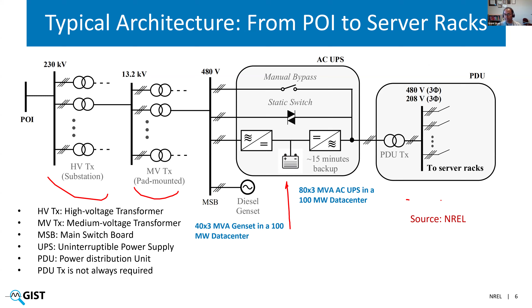What I want to focus more on is what is there within the IT rack. So we start with 480 volts today. Previous data centers were more towards 208 volts. And then we have these power supply units, which are hot swappable and arranged in a power shelf, where multiples of three are arranged in a single power shelf, because they're all single phase converters, but they are supplied by a three-phase supply. So they're distributed either using star or delta connections.